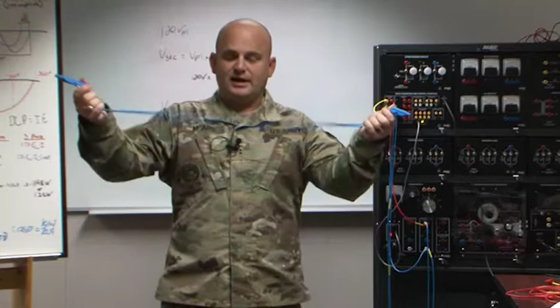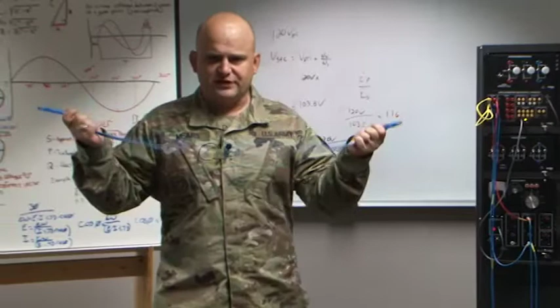But now, if I take this same conductor, one of equal value, same length and size, and hook these two ends together so I have two of them in parallel, what did I do? I added more material. If electrons want to travel along the surface area of the conductor and I give more surface area, more conductor, more material, I'm doubling the ampacity of this circuit. By putting something in parallel, I'm providing more capability to the circuit.